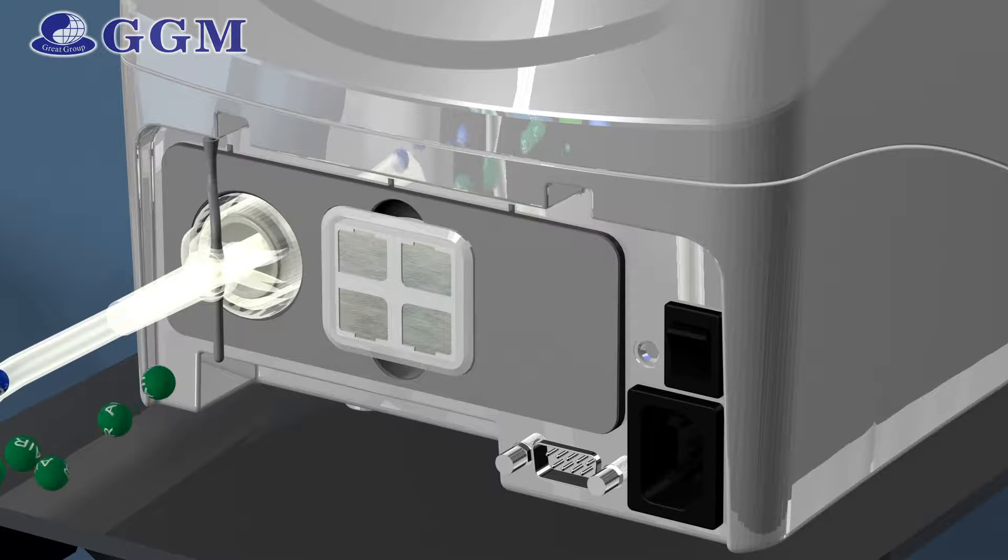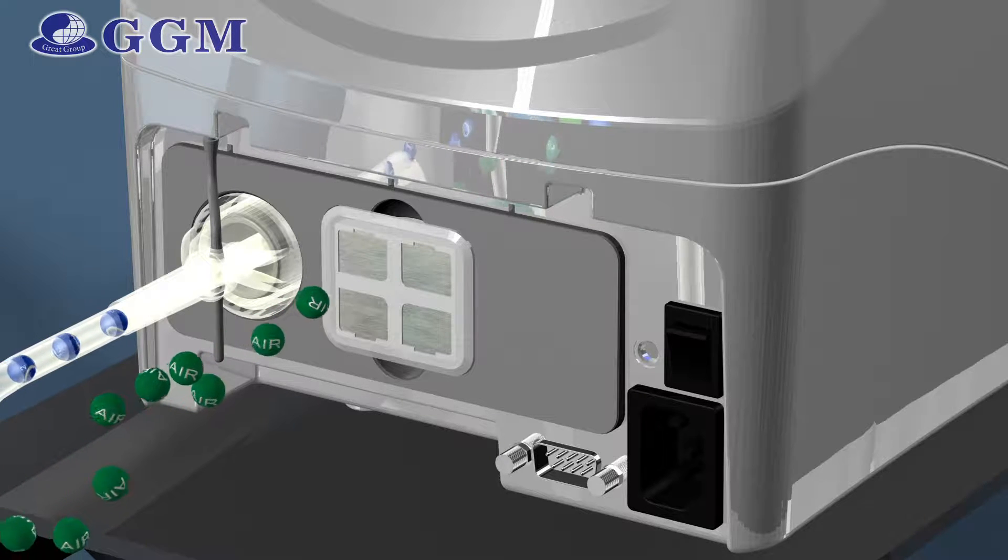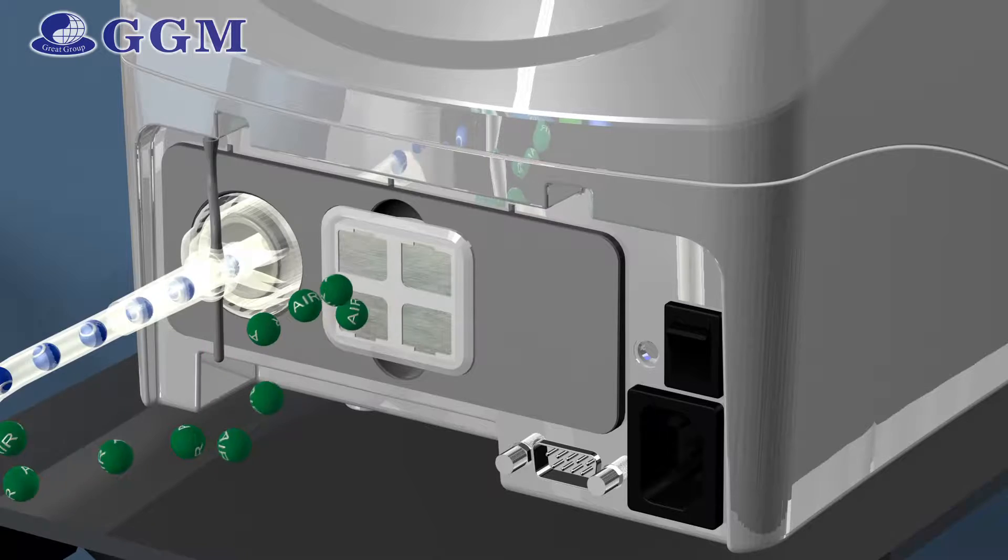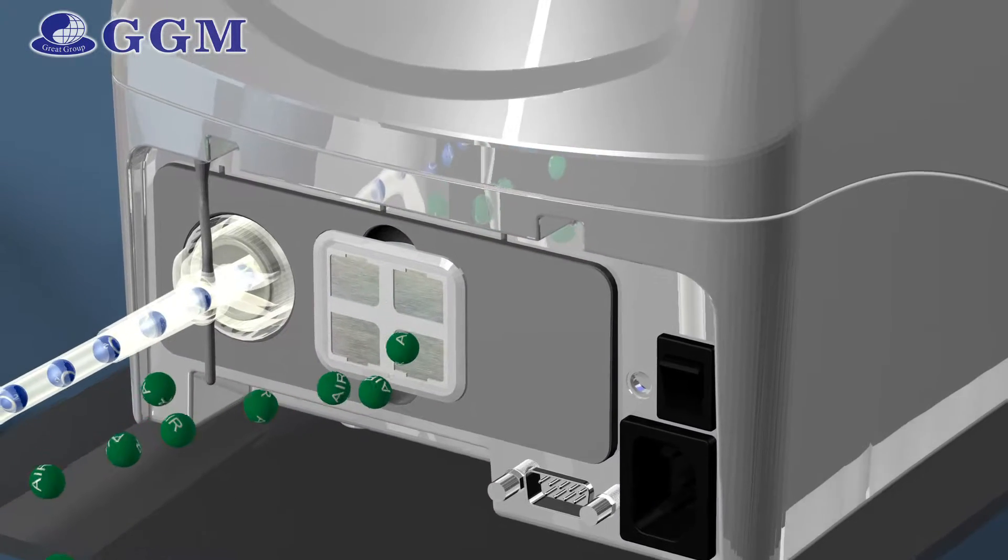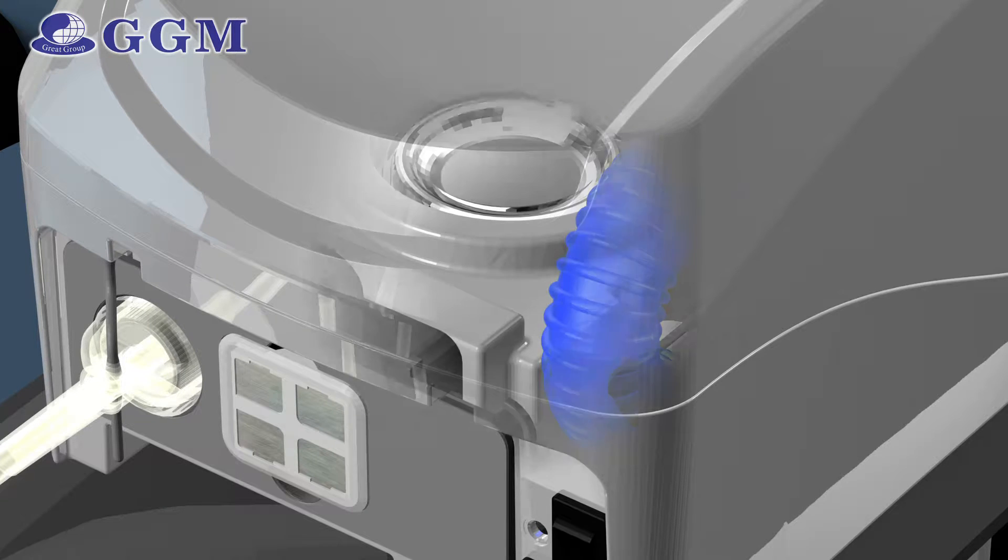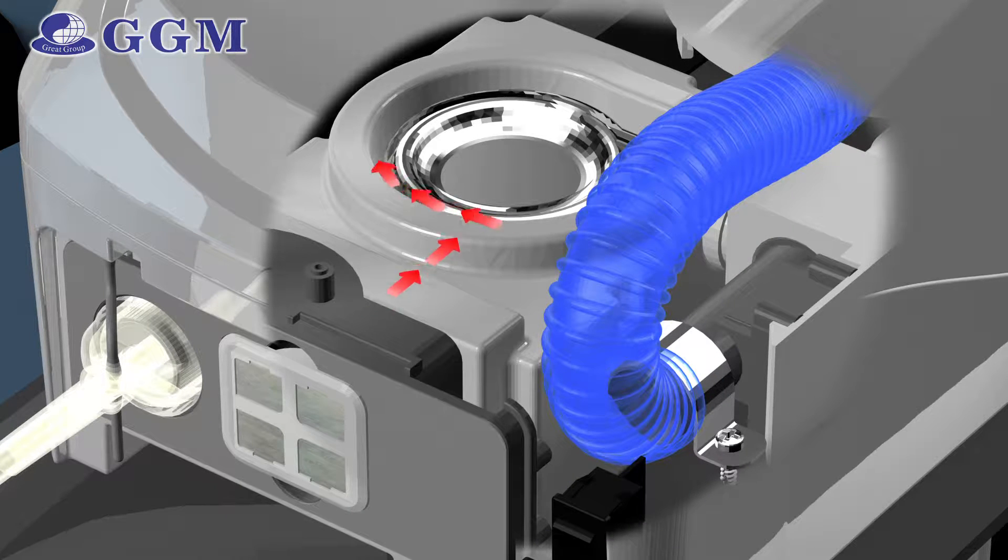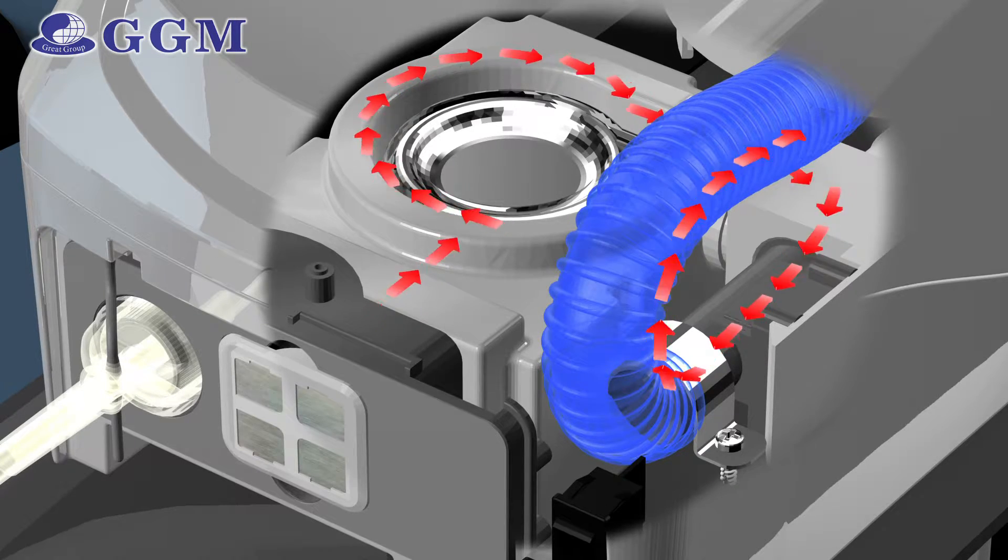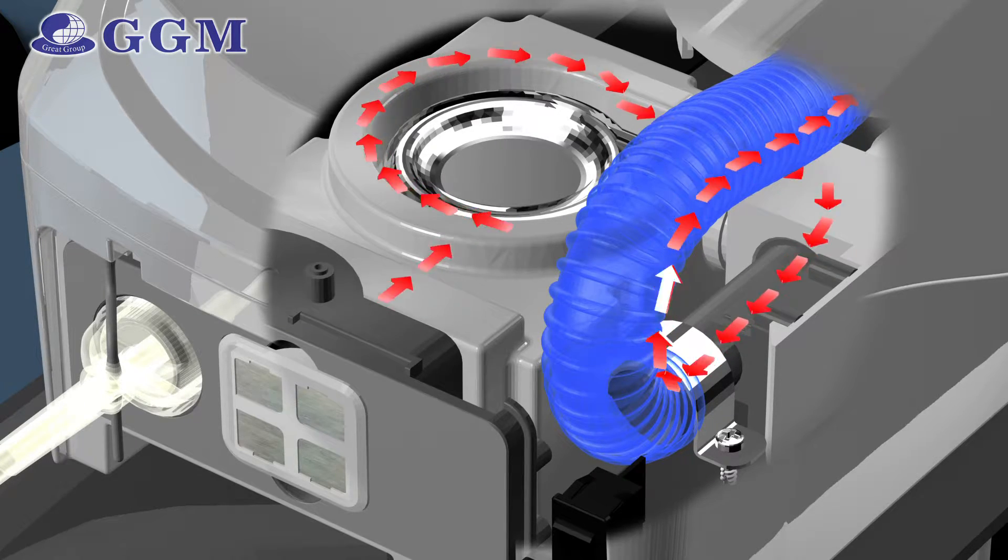Room air and oxygen are collected by a quiet motor through a filtration port. Before entering the flow generator, a blending space is provided to allow the oxygen and room air to evenly mix. The flow generator creates flow from 5 to 15 liters per minute for infants and 15 to 50 liters per minute for adults.